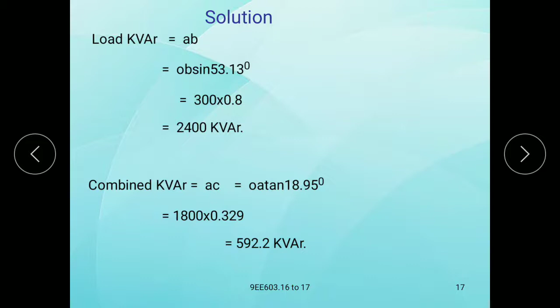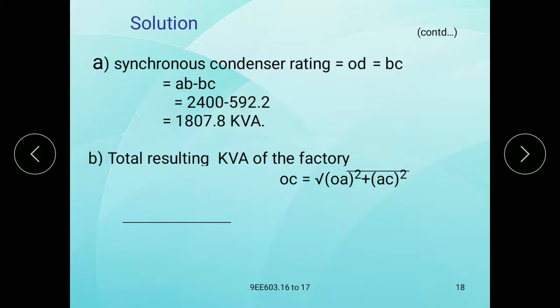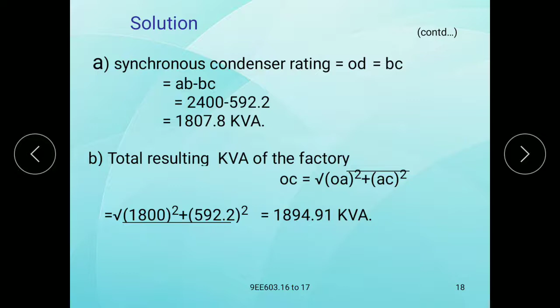Now the synchronous condenser rating OD is equal to BC, that means AB minus AC, that is 2400 minus 592.2, which gives 1807.8 KVA. So the total resulting KVA of the factory, OC, is equal to the square root of OA squared plus AC squared, that is the square root of 1800 squared plus 592.2 squared, equal to 1894.91 KVA.